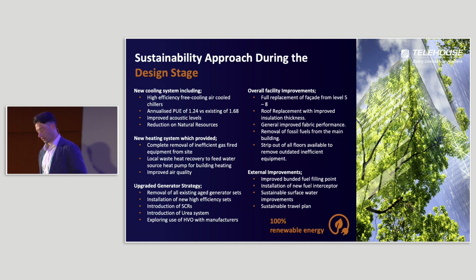So, our improved acoustic levels. Obviously we have neighbours around the vicinity as well. We have a hotel beside us and plans for a new residential development right beside us. So we had to take them and our local community into consideration during the fit-out of this building. So we have improved, massively improved, acoustic levels, and a reduction in natural resources as well. Our cooling system in this building doesn't use any water, so it doesn't use any natural resource for cooling, no adiabatics at all. It's a standalone chiller and it keeps operating as air-cooled.